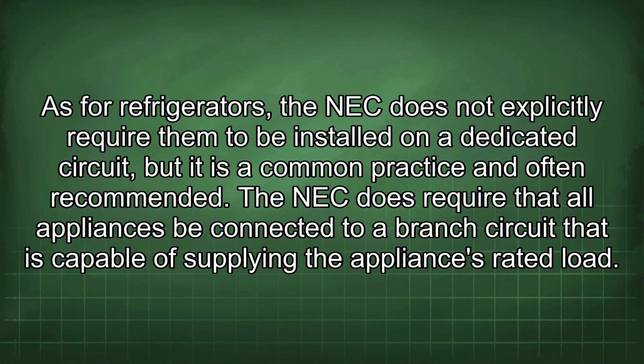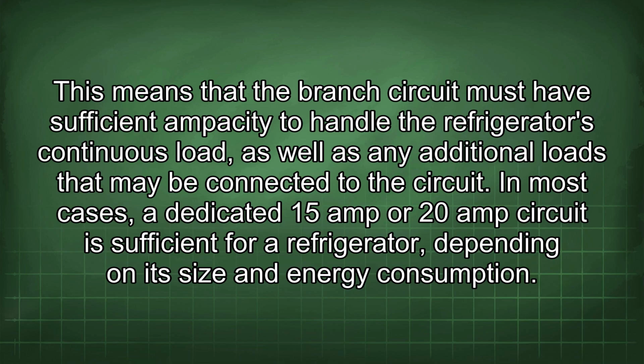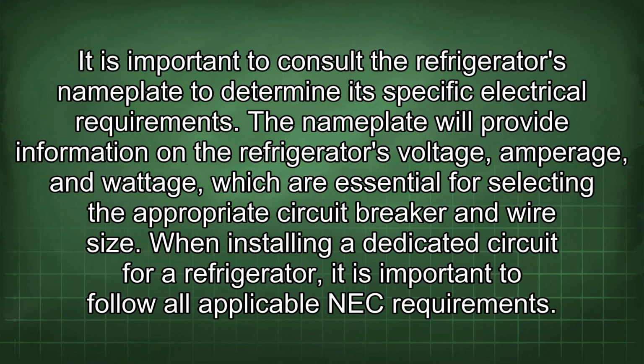As for refrigerators, the NEC does not explicitly require them to be installed on a dedicated circuit, but it is a common practice and often recommended. The NEC does require that all appliances be connected to a branch circuit that is capable of supplying the appliance's rated load. This means that the branch circuit must have sufficient ampacity to handle the refrigerator's continuous load, as well as any additional loads that may be connected to the circuit. In most cases, a dedicated 15-amp or 20-amp circuit is sufficient for a refrigerator, depending on its size and energy consumption. It is important to consult the refrigerator's nameplate to determine its specific electrical requirements.